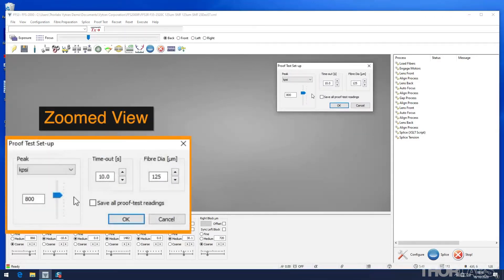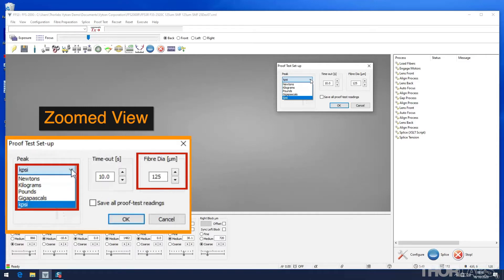The proof test parameters can be set in the software by either selecting proof test from the upper menu items or right clicking on the proof test icon in the main toolbar. A variety of units can be selected for the proof test measurement. If KPSI or Giga Pascal are selected, it is important that the fibre diameter corresponds to the fibre being tested.